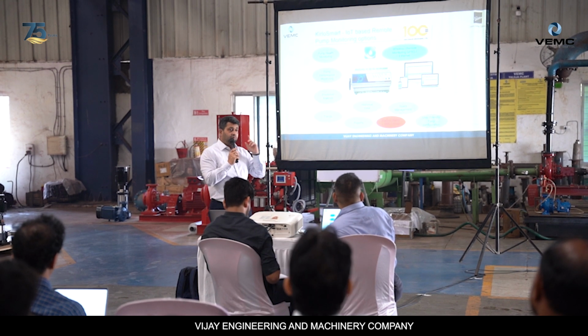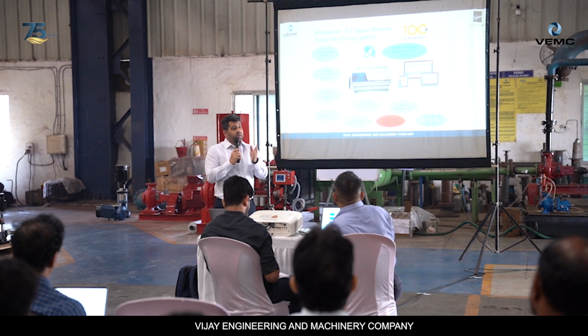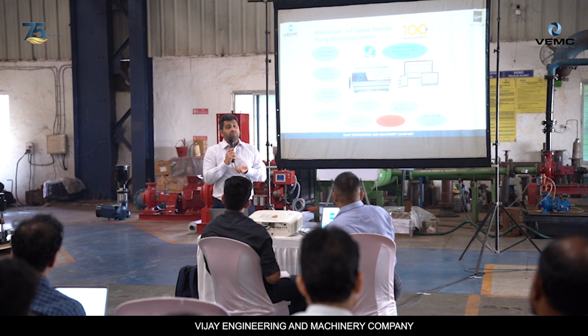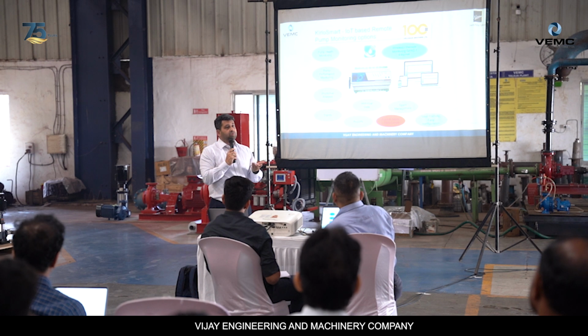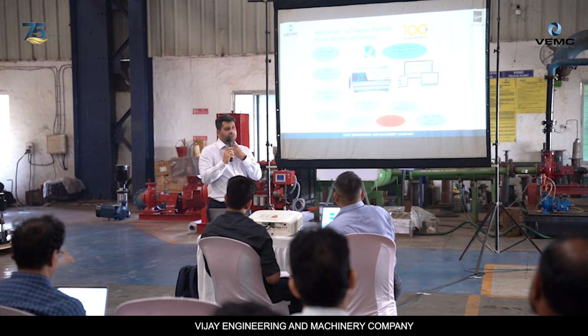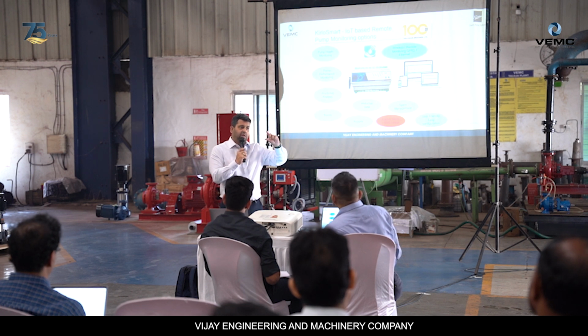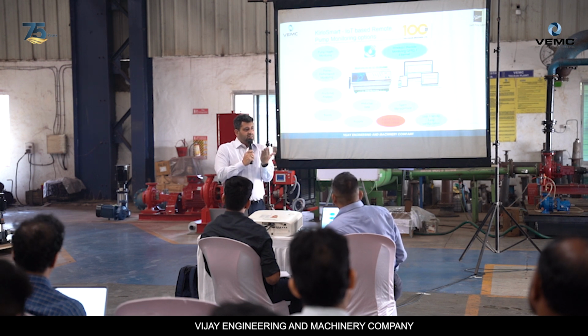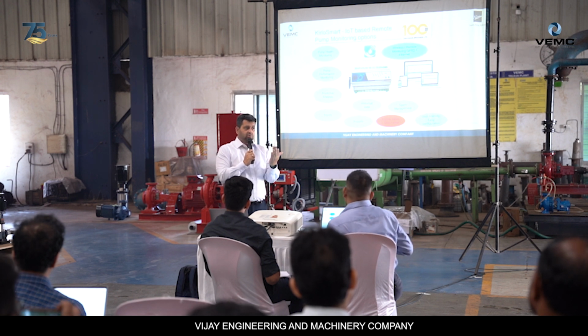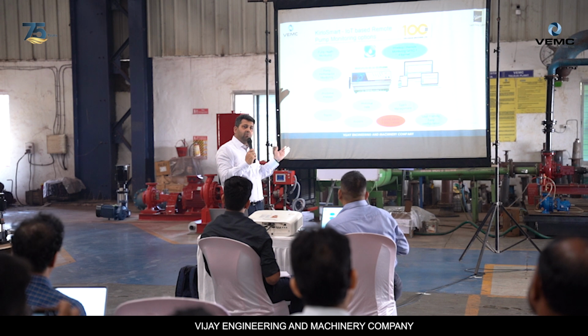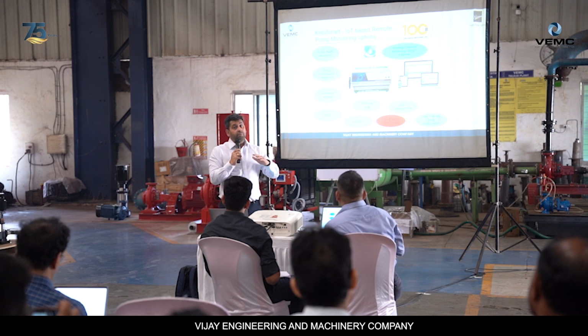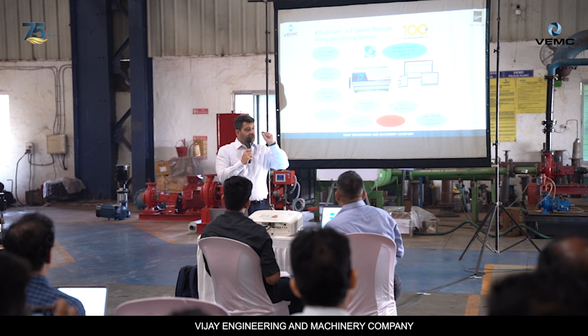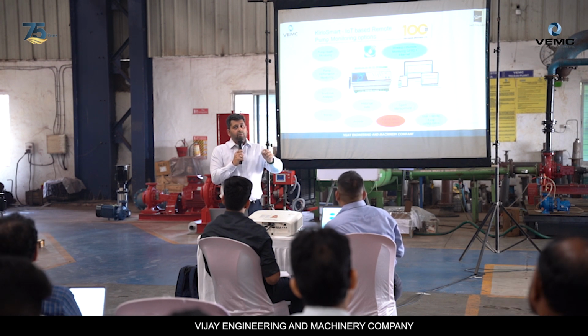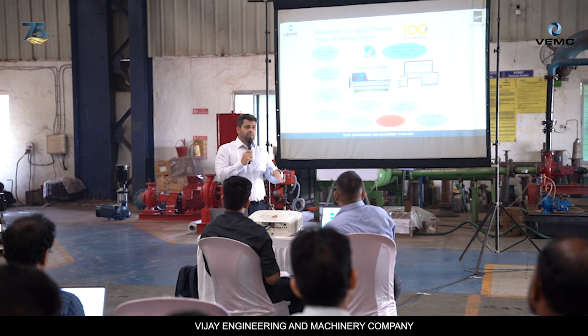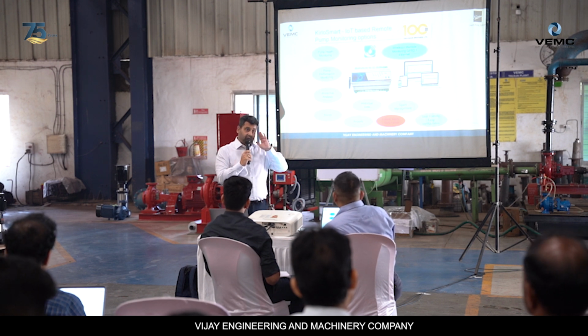From a fireman's perspective, you can also see what operations are happening. Are they testing the system? What other operations are happening, what kind of data are we capturing? Once the data is available, it would be as good as a semi part of your FM UL system. The FM UL system is nothing more than this: it records the data so that the insurance company, Factory Mutual, can clearly identify and state that the system was running and operational during a fire. This system will identify whether it was operational or not, and it will be available through third-party software. Currently it's a SIM-based system we are offering; in due course we will have a Wi-Fi system in place, as long as there is connectivity, because your pump houses may be in basement 1, basement 2, and so on. So this is something one has to keep in mind.